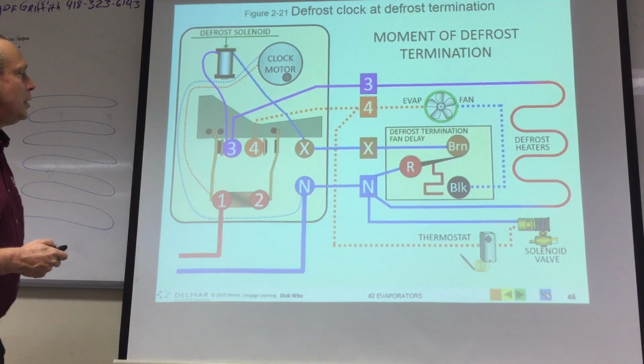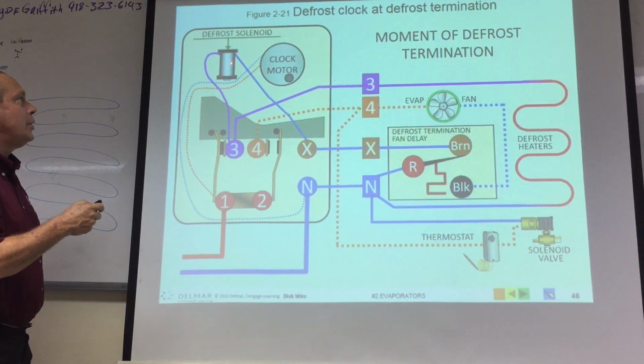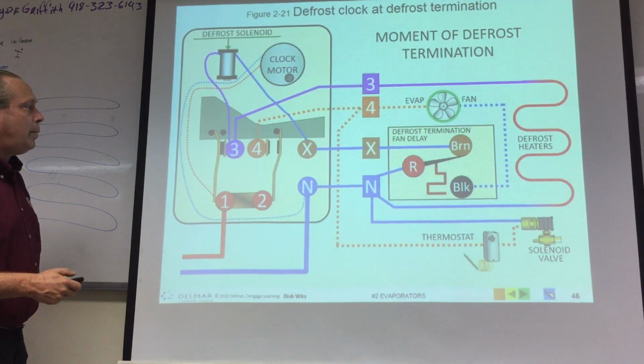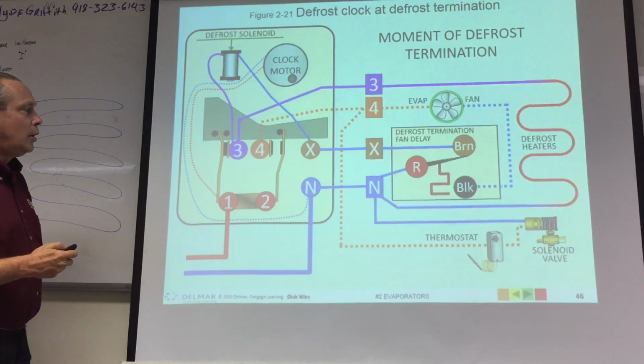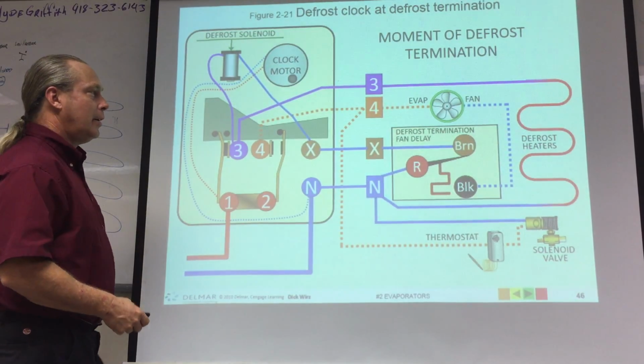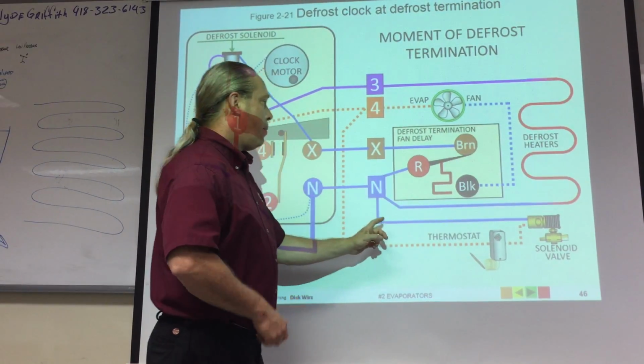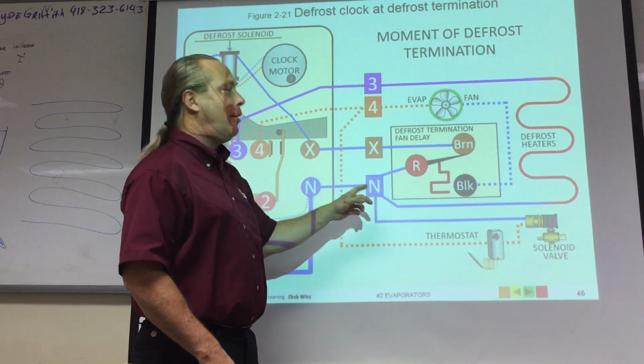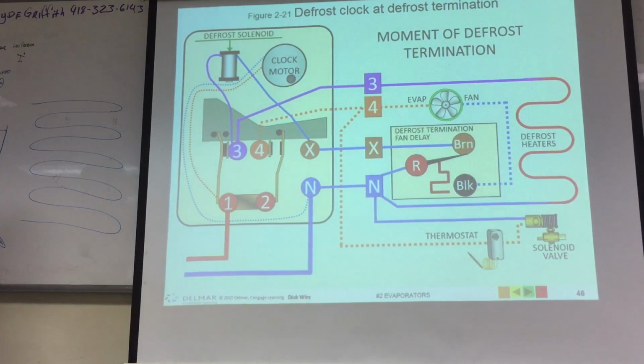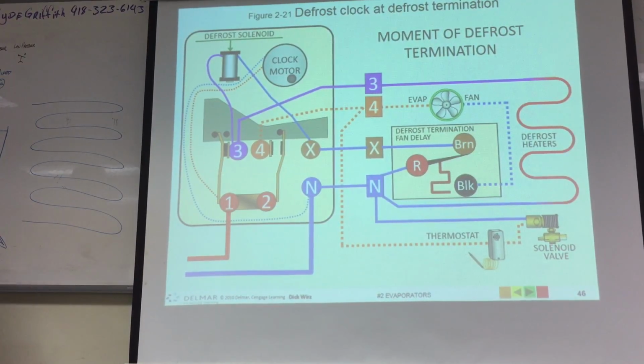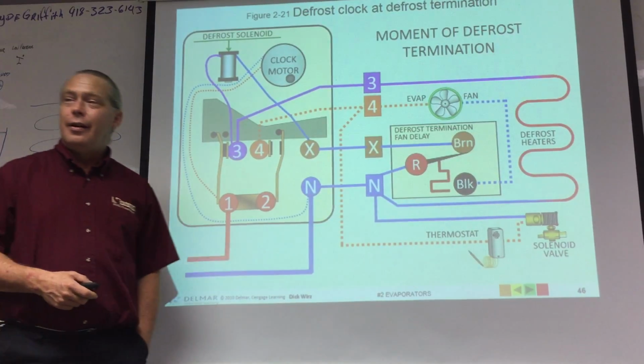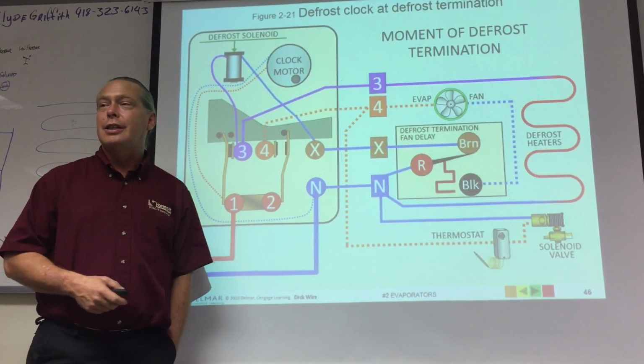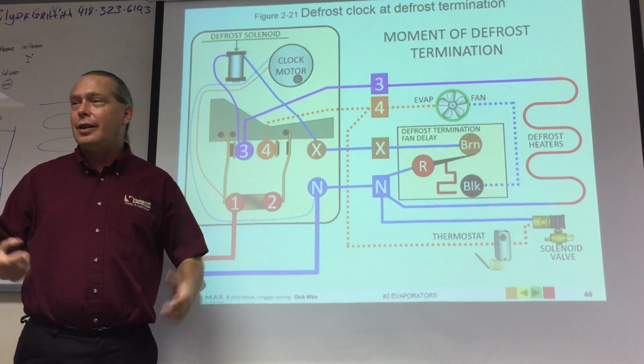Now we've got neutral to X. Power is already going to the defrost solenoid. Now it has a path back to neutral, and that is going to break our connection to the defrost heater. The fan, however, will not be able to come on until the coil has got cold enough to remake the connection to the black wire. Because we might have a 50-degree coil in a box we're trying to keep at -20. Do we want the fan coming on when we have a 50-degree coil? No, let's let that coil get down to what? 30 at least.